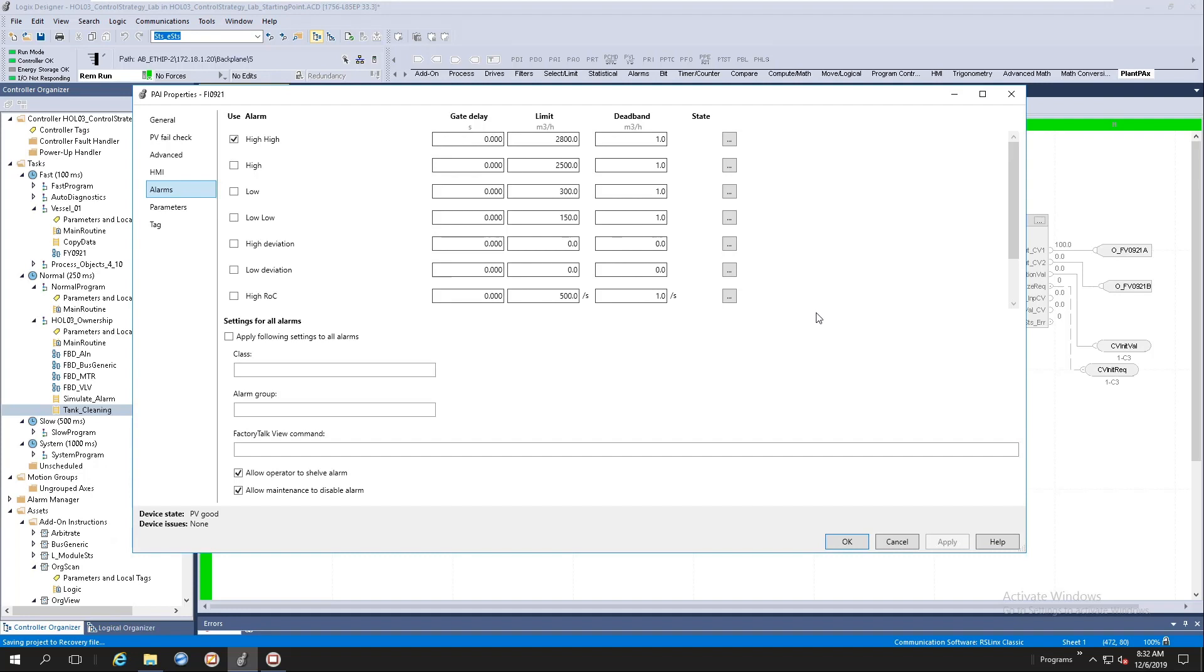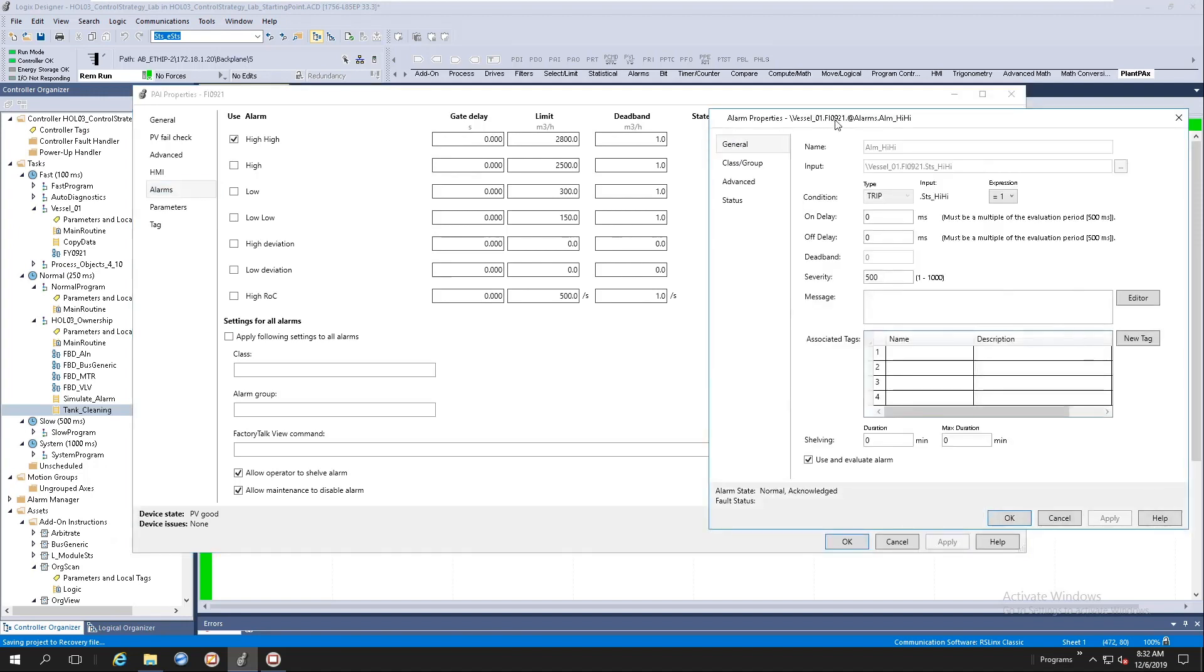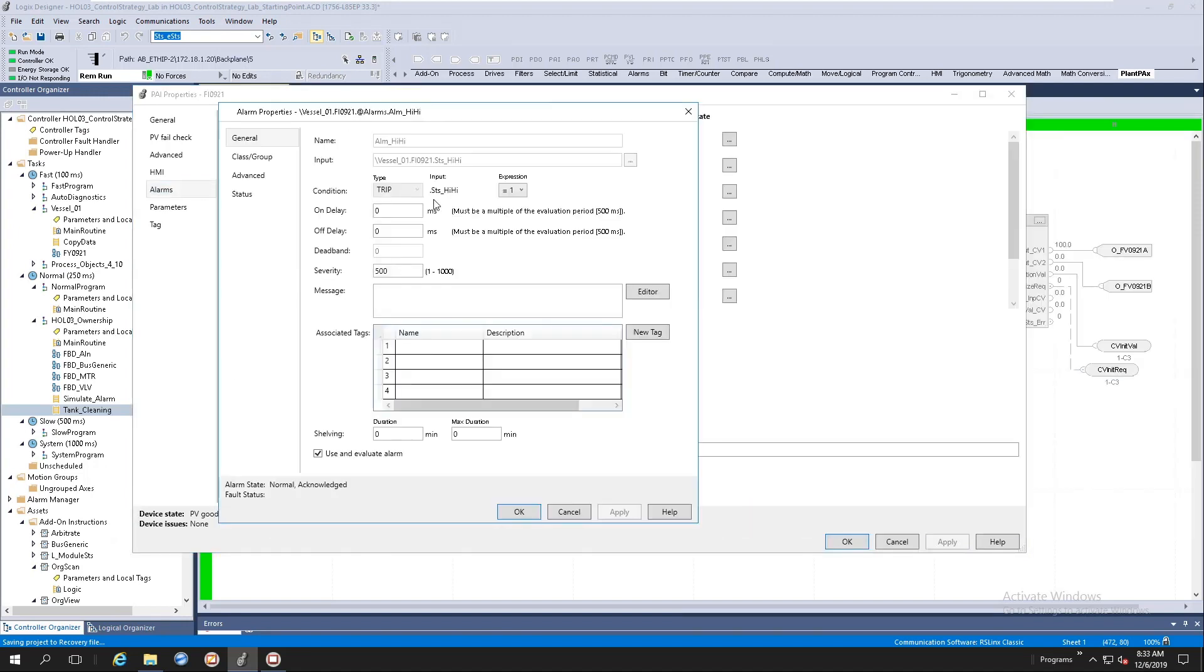If we look at here at the right hand side, we've got a thing called state here. If we click on the state ellipsis box, it will actually open up the logic tag based alarm dialogue property panel. Typical configurations that you'll get here is your on delay, off delay, severities, alarm messages, shelving durations...